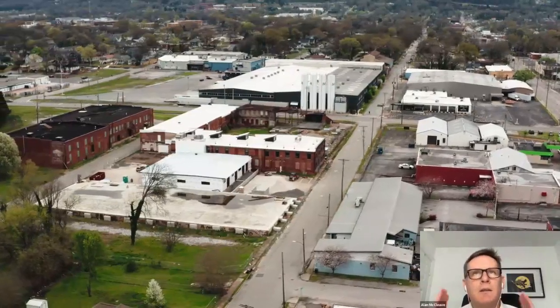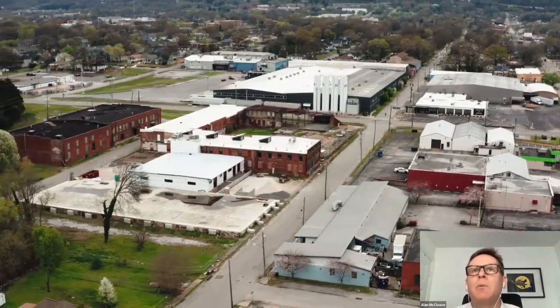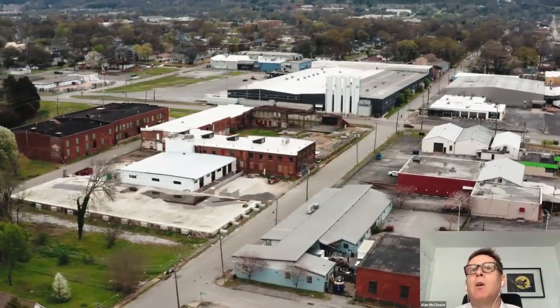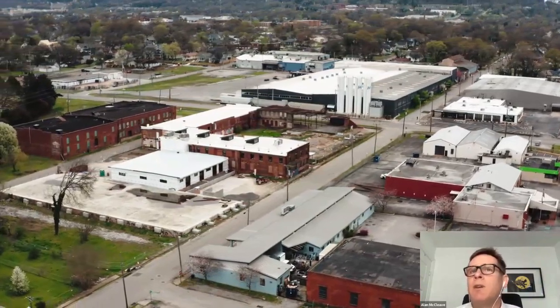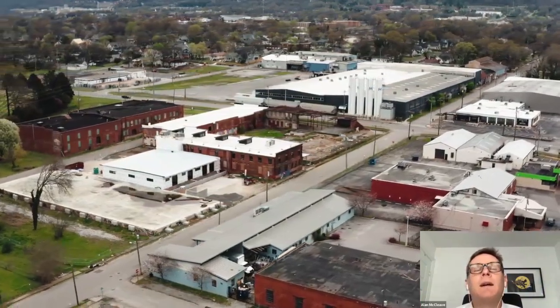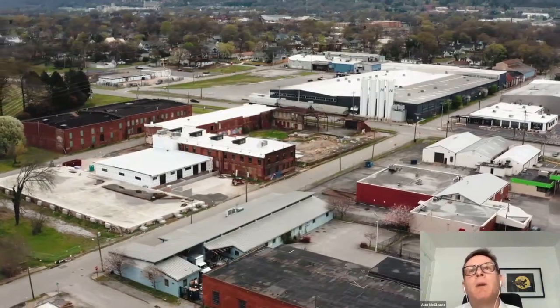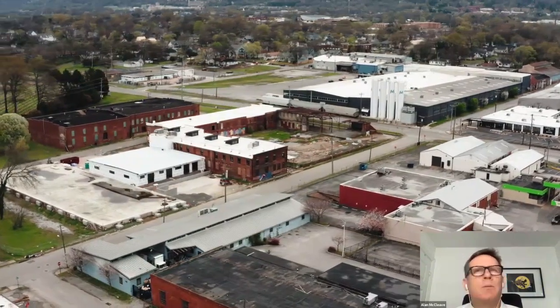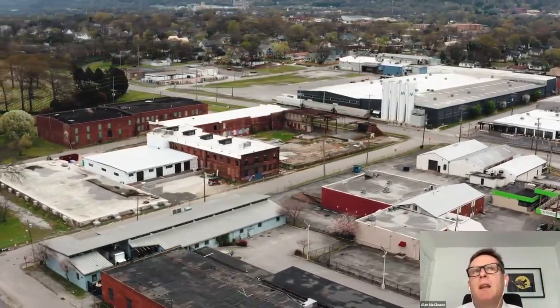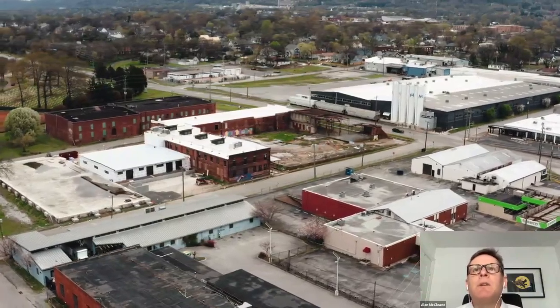If we take an example, a typical business site might have 70 kVA of power supply coming into the building. If you've got hundreds of kVA, you're very lucky or you've got a very big site. A typical site might have 70 kVA, and maximum demand could be something like 35 kVA to keep the numbers simple. That means your available supply is 35 kVA, which converts to roughly 30 kilowatts.